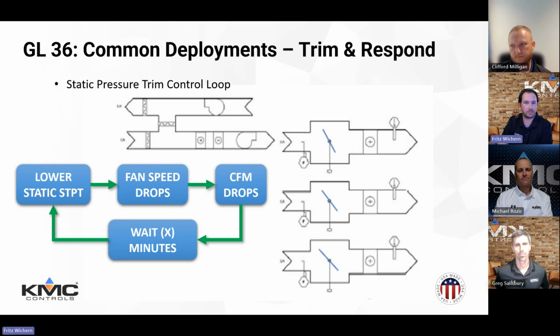And then the one last piece of this, I guess, is just once there is a call for cooling, increase the static pressure from the air handler until the calls are satisfied. These changes are made gradually, usually approximately 0.1 inches every 15 minutes. And it's adjustable, set up by your designer or engineer. So there's a lot of data flying around.